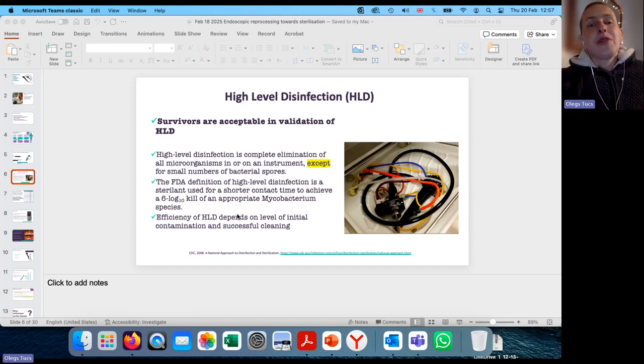But the big difference here is that all you have to do to validate that process is to make sure your numbers have come down 1,000,000 times. And if you start with a trillion microorganisms on a scope and you put it dirty in the endoscope reprocessor, it will bring numbers down 1,000,000 times from a trillion to 1,000,000. And we have a million survivors at the end of the process, which technically meet the criteria for high-level disinfection. Like, it's obvious nonsense, of course. So the efficiency of high-level disinfection depends on two things. How much contamination, how much bacteria was present on an instrument before the start of the process, and how successful was the cleaning.